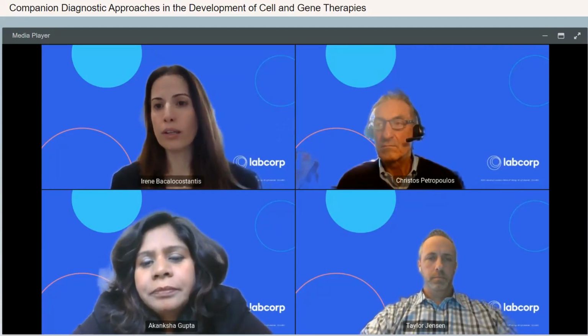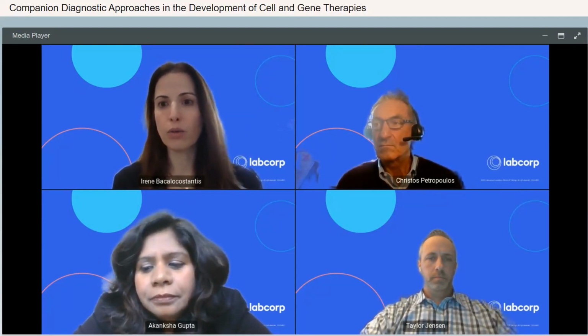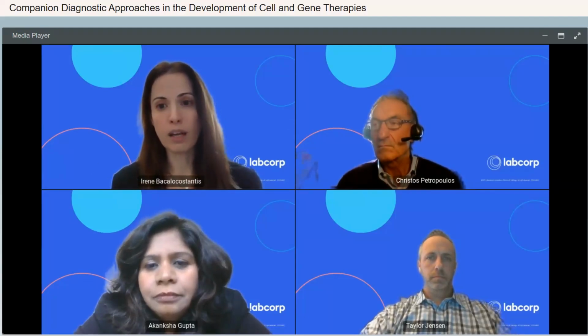Because what it looks like right now, whereas in the US there is that parallel review, and the expectation is that CDRH and either CDER or CBER will have that approval on the same day, that sort of framework does not exist yet in the EU. So your notified body takes as long as they need. We've been informed by our notified body that they'd like to complete their review in under a year. That's their preference. So we assume about a year.